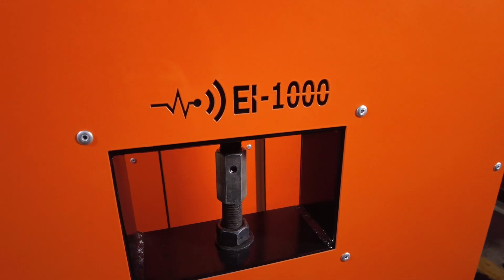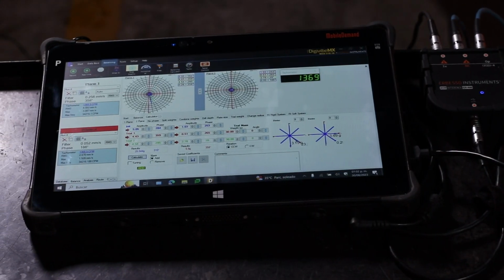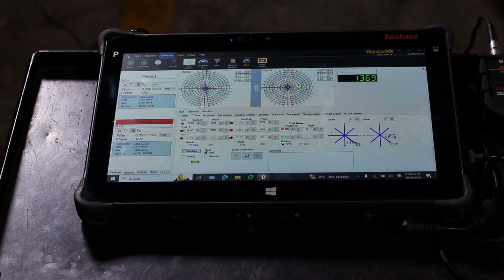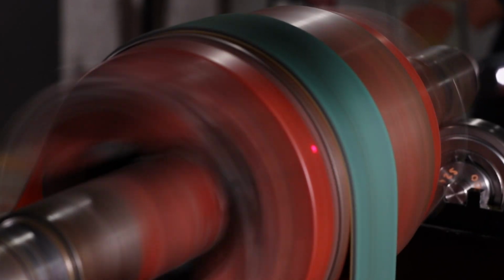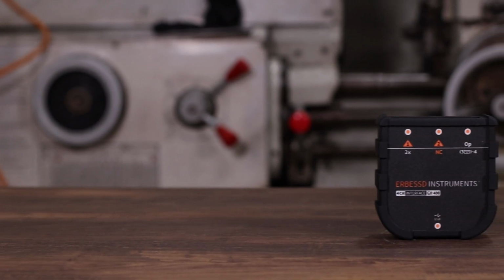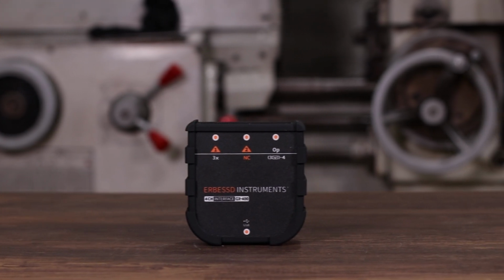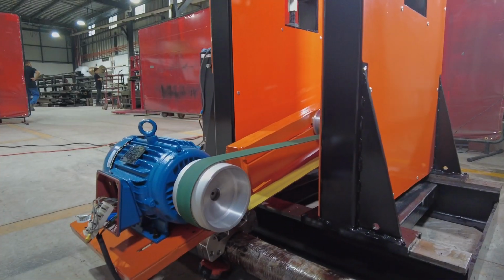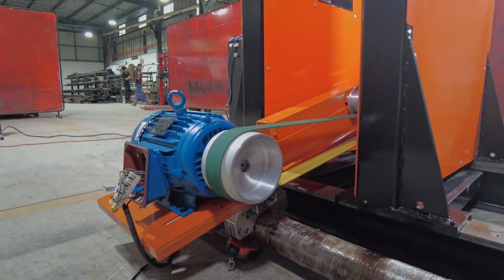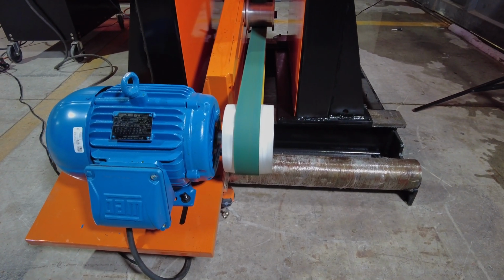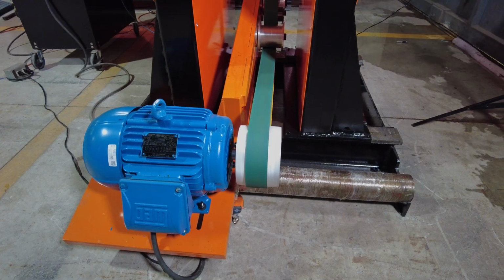And soft bearing suspension balancing machines don't rely on load cells, and instead, soft bearing machines rely upon using acceleration as a measurement, using accelerometers, and using a tachometer for phase reference. So combining those two allows the customer, from a calibration perspective, to only need to have your sensors calibrated, which is quick and easy and can be sent to almost any calibration laboratory around the world. The other benefit to a soft bearing suspension balancing machine is they don't have to be fixed to the floor. They just have to be installed generally on a fairly flat surface. So in some cases, we've actually seen soft bearing machines installed on flatbeds for tractor trailers and with jack stands so that the flatbed remains stable during the measurement process.